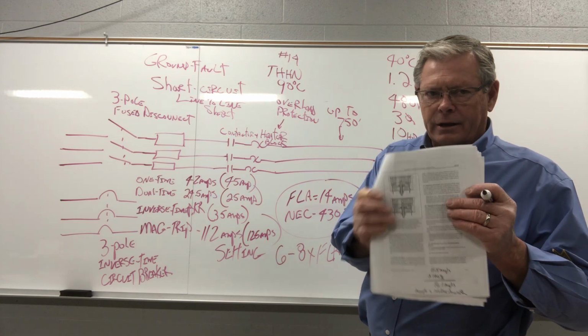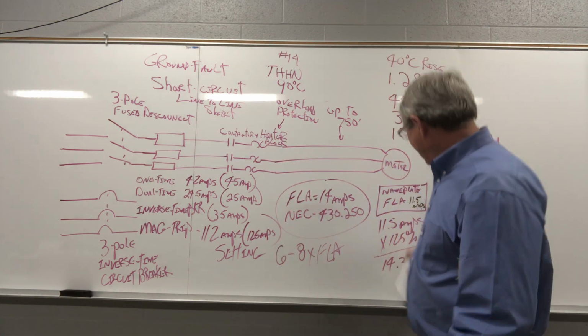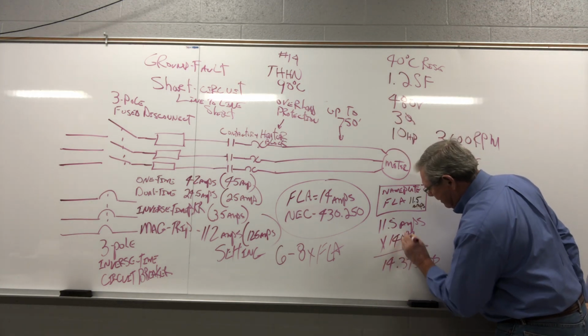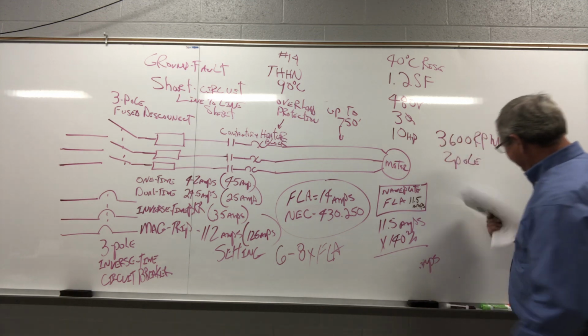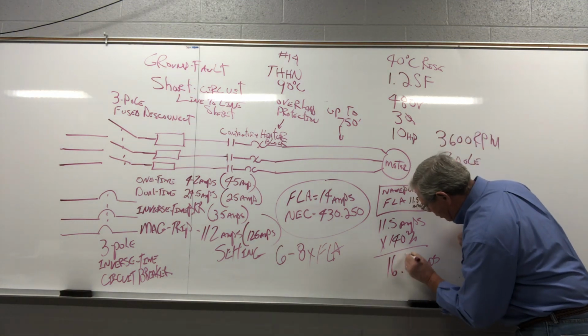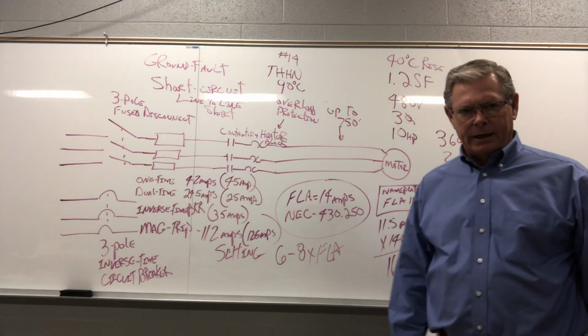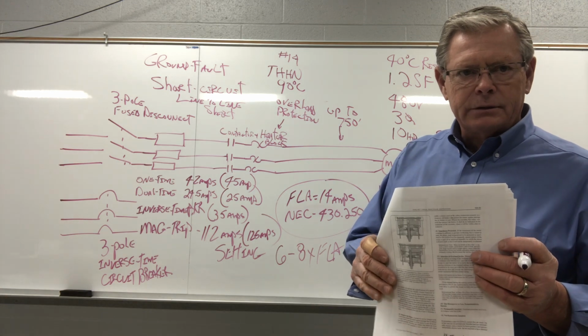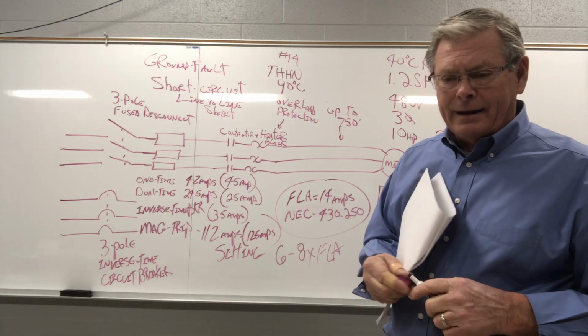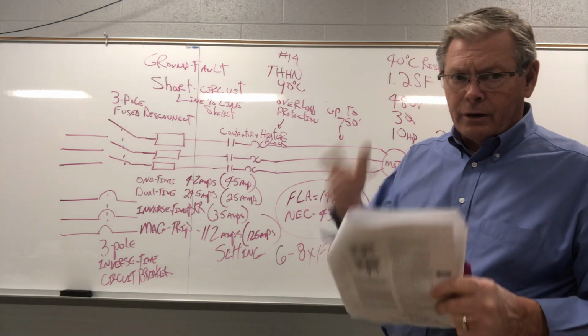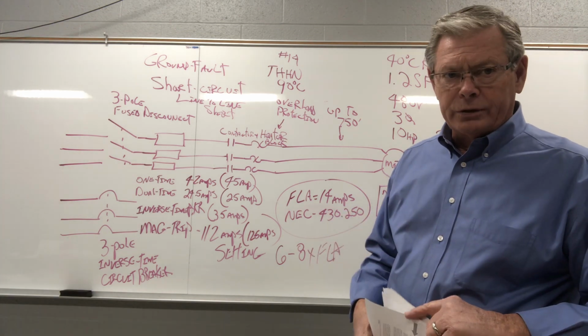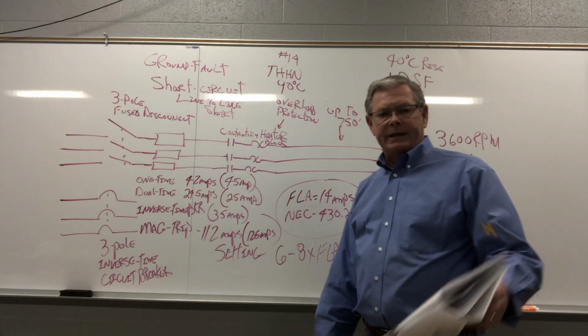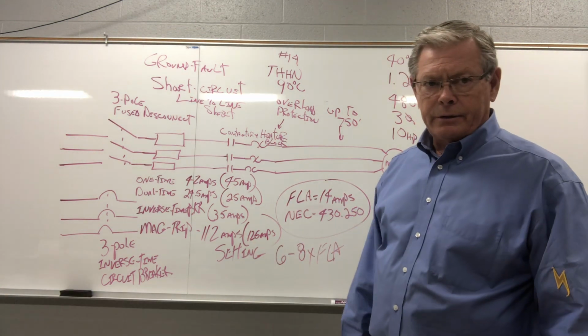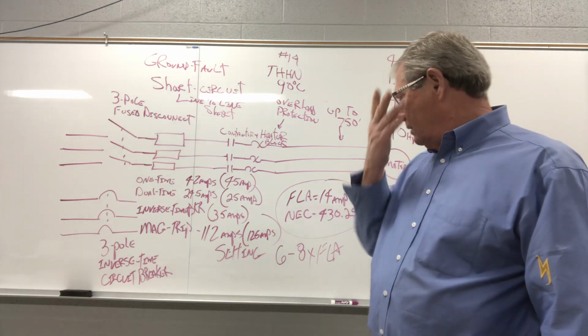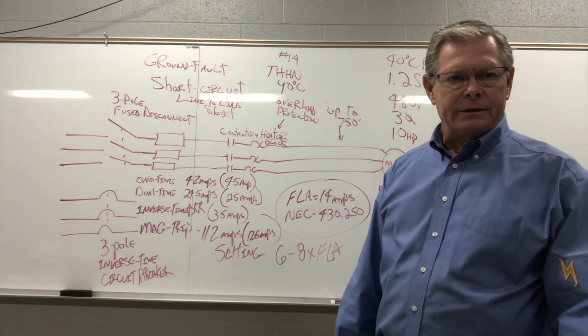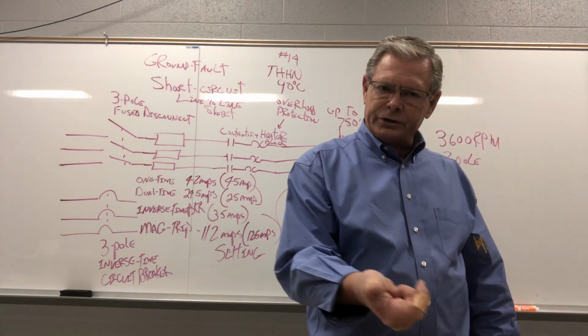The next page here on the handout says that we can go, instead of 125%, we can go to 140% of nameplate, and we can go from 14.375 to 16.1 amp heaters, okay? And still have motor protection. So, if we know that, we can do a whole lot of troubleshooting with our own noggin instead of changing motors out, right? So, if you don't know this, and let's say that you're on a production line and they're trying to run material that's heavier than normal. If you don't know this and you say, well, the motor's tripping out all the time, we just don't have a big enough motor. Well, let's put a 15 horse on it instead of a 10.